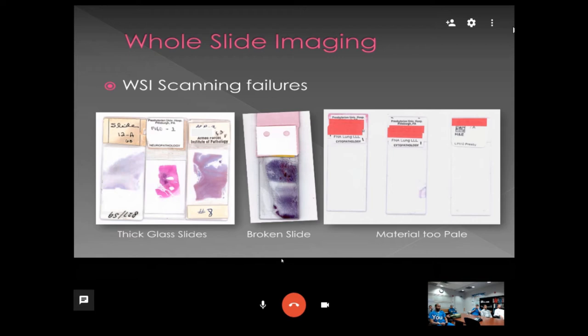However, they may be able to be manually scanned, depending on how the whole slide scanner grips the slide. If the slide is broken at the slide label, the whole slide scanner has to grab that glass slide from the slide label, so that slide will have some scanning failures. And then depending on the tissue recognition, if some of the material is too pale, the whole slide scanner may fail that scan as well because it doesn't recognize any tissue on the slide.